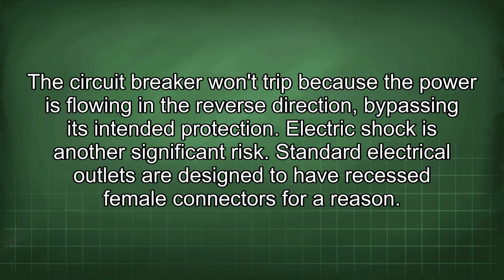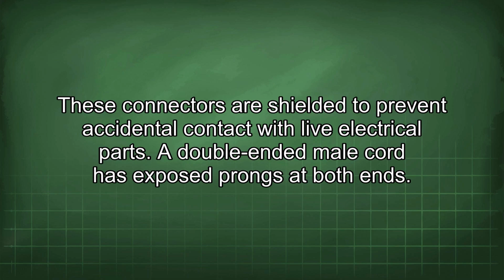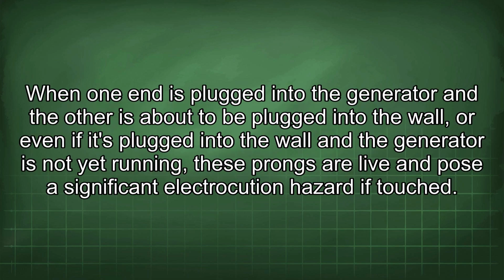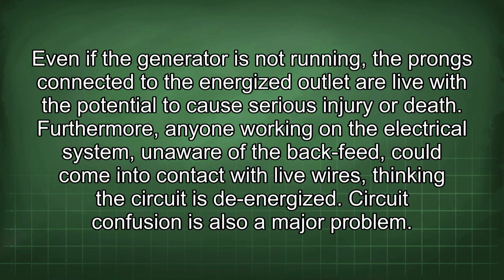The electric shock is another significant risk. Standard electrical outlets are designed to have recessed female connectors for a reason. These connectors are shielded to prevent accidental contact with live electrical parts. A double-ended male cord has exposed prongs at both ends. When one end is plugged into the generator and the other is about to be plugged into the wall, or even if it's plugged into the wall and the generator is not yet running, these prongs are live and pose a significant electrocution hazard if touched. Even if the generator is not running, the prongs connected to the energized outlet are live with the potential to cause serious injury or death.